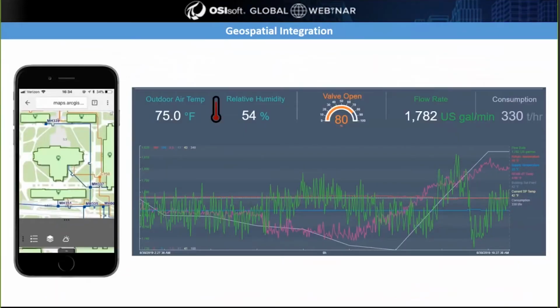Now we've come from the geospatial landing page to the data for chilled water consumption at a single building. This screen is a template, with key parameters listed: outside air temperature, relative humidity, flow rates, consumptions, and valve positions. The value of this screen being a template is that we only build it once, and because of the structure of data within the PI system, it automatically populates with data from each building.